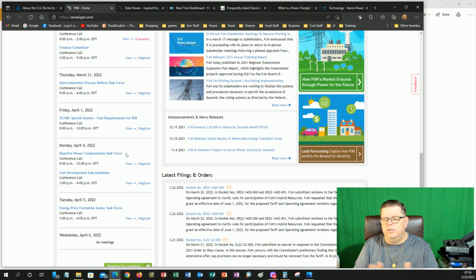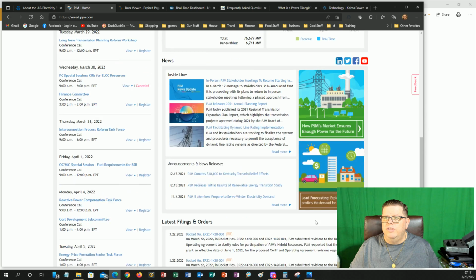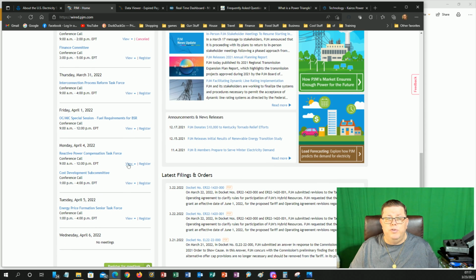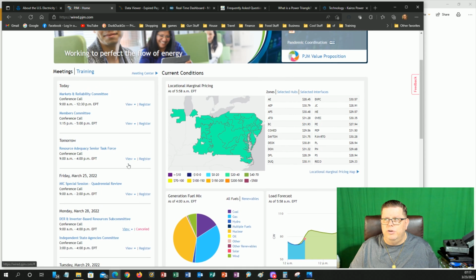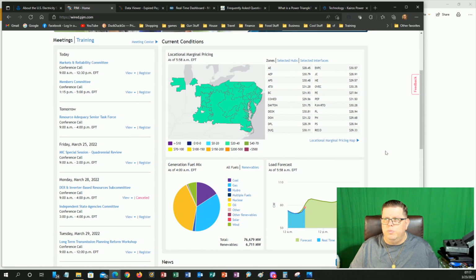Again, it's more than you want to know, and it's probably boring to most of you, but there are other things out there. It all boils down to cost. If you're not getting paid for reactive power, who cares if you produce it or not, from that generator's perspective? They get paid for megawatts, for real power, so they do some reactive support, but it'd be nice if there was reactive compensation for generators. Then maybe the design of their generators would change to give more voltage support, and that gives more stability to the grid, fewer blackouts, fewer issues, when you have that voltage to prop up the grid and push power from the generation to the load.